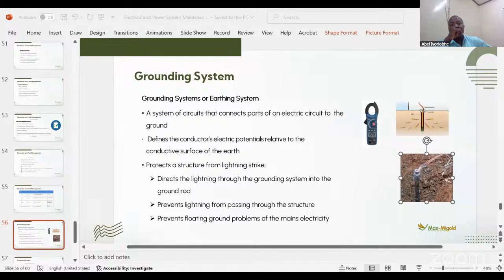Okay, yeah, that effect you have expressed is called the Ferranti effect. Ferranti effect is an instantaneous increase in voltage, as if people start dropping their load - maybe the light - you are running on light load at the receiving end, it is called Ferranti effect. What you need to do is maintain a certain value of load, just like 45% of your load, it will reduce the effect of Ferranti effect.